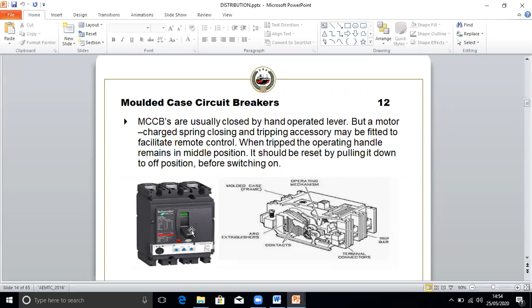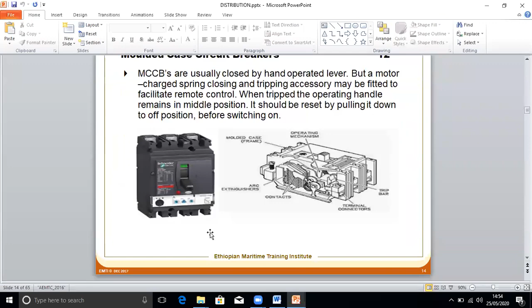So like a boiler panel. The main switchboard will have feeder circuit breakers for the boiler, IG plant, steering gear, air conditioning. All will have feeder circuit breakers like this, MCCBs. We don't use the MCB. MCB is a very low capacity one, and it is used only inside the distribution board.